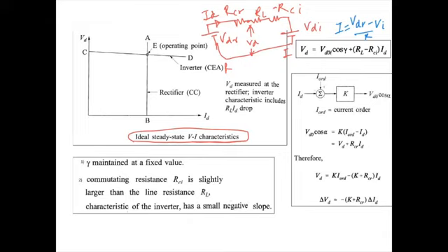So there is one control scheme provided to the rectifier which keeps the current in the HVDC link constant, and this characteristic is called the constant current control characteristic of the rectifier. You can notice that the line AB, which is vertical, represents the constant current control characteristic.